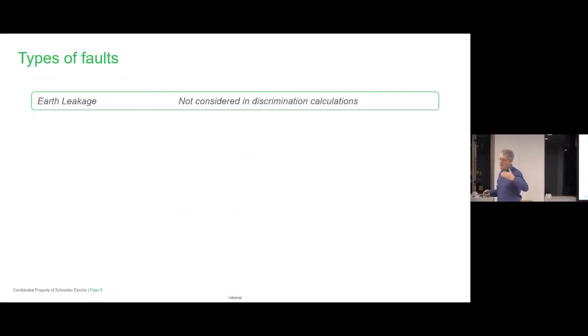because they apply it from the source all the way down to final distribution. They're very good at doing it. They know what they're doing with it. They have a different system that they operate on. Ours is TN-C, but they use IT. They have a lot of different systems there where earth leakage works better.